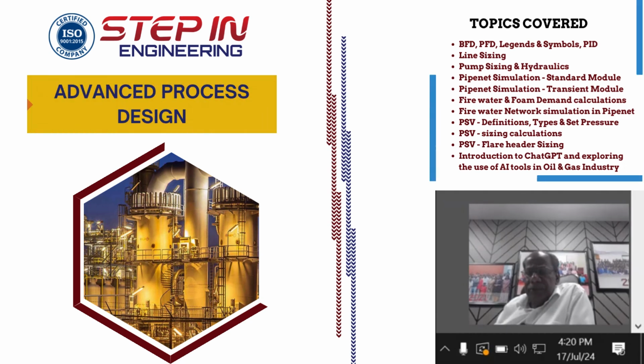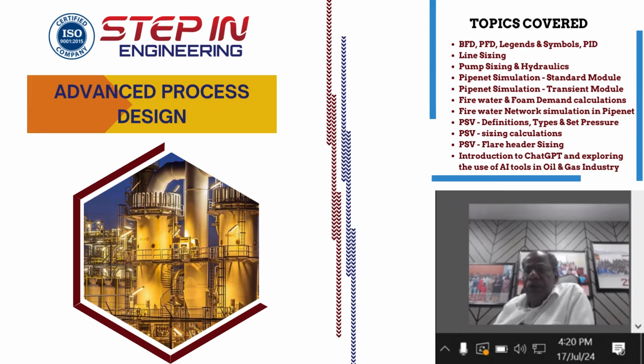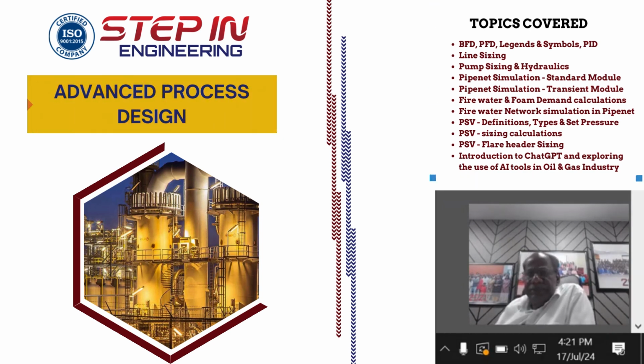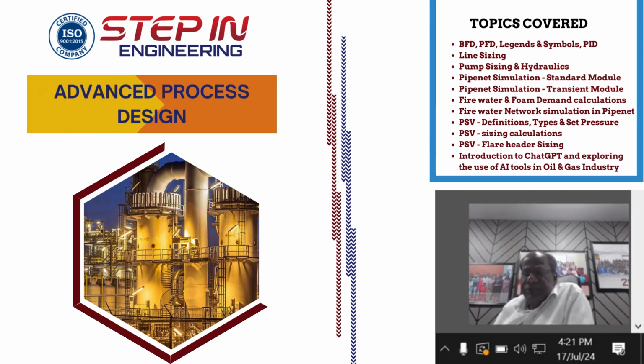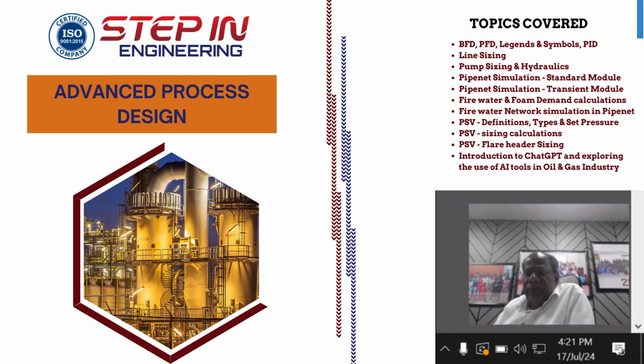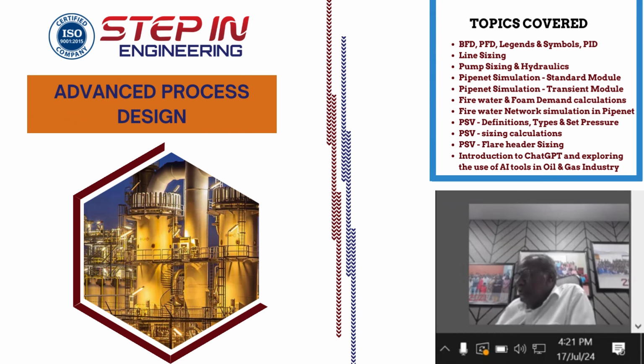We are going to talk about the line sizing for single phase. If it is going to be a pure liquid, what is the criteria as per API 14? If it is going to be two phase, what is the erosion velocity? How important is it? Then how do you calculate the erosion velocity? When I talk about the erosion velocity, the C factor, if you look at API 14, where it is stated, how much is the C factor? It can vary from 100 to 250. Then what value will I take, based on which? All this will be discussed in the line sizing.